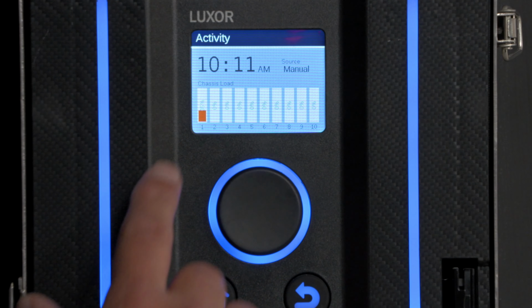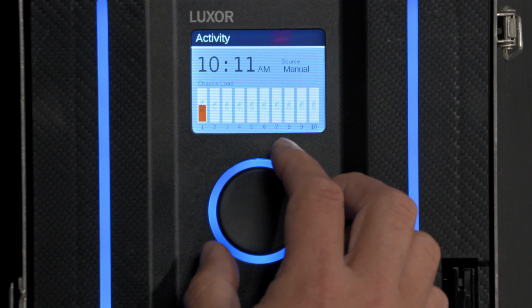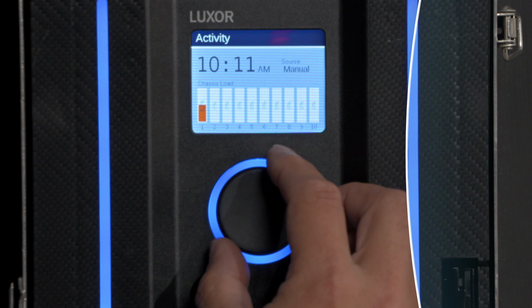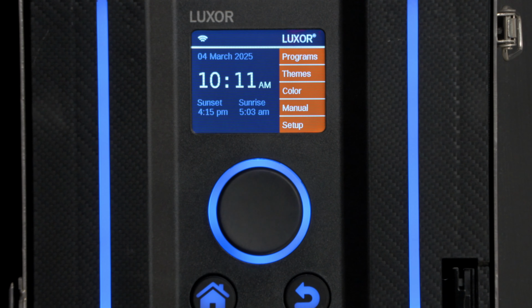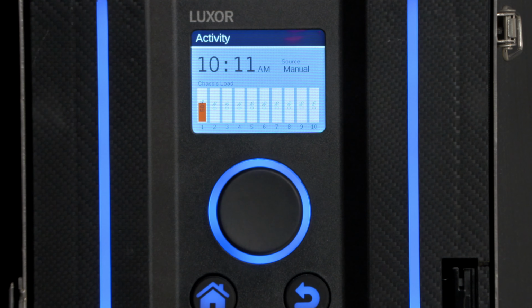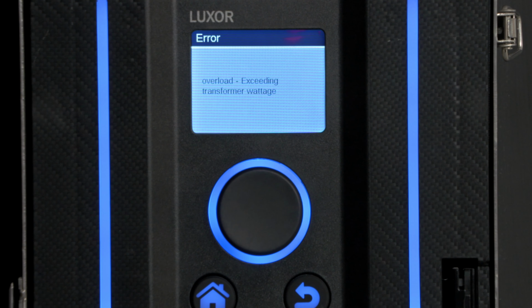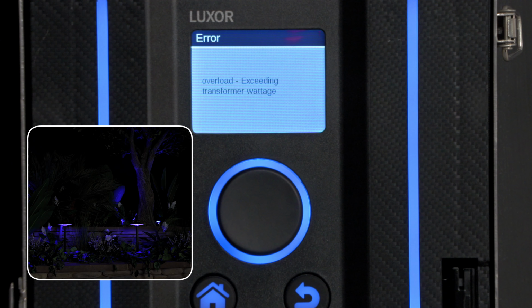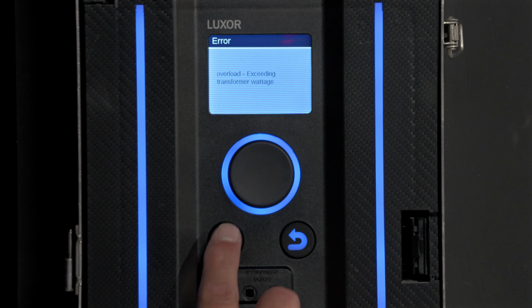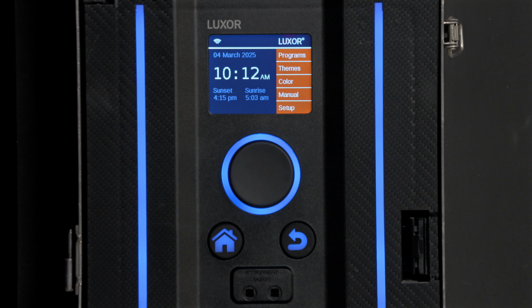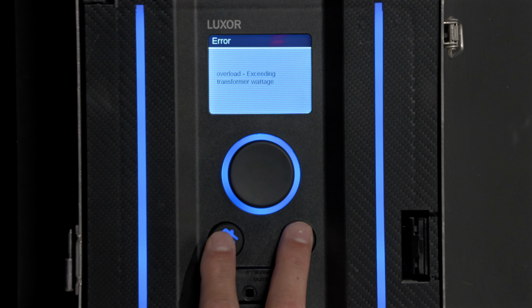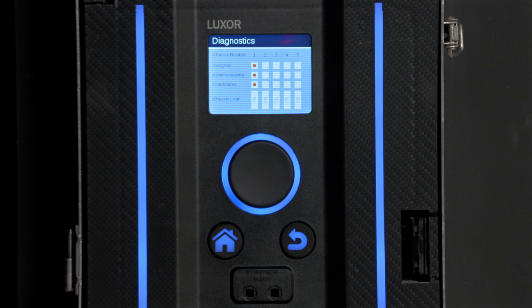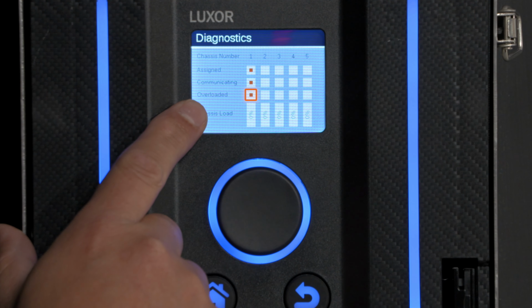From that activity screen, you will also be able to see the different load percentages of the chassis. If the system is overloaded, an error message will pop up saying, "Overload exceeding transformer wattage," as soon as the controller is turned on to power lighting fixtures. The system will immediately shut off. When you return to the home screen, the message will temporarily clear, and then continue until the issue is fixed in the field. To determine which transformer overloaded, press the home and return button at the same time to go to the diagnostic screen. The overload section will be highlighted in orange to identify the affected transformer.